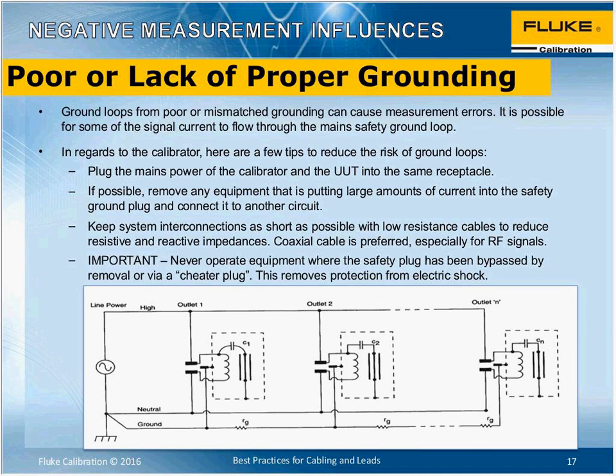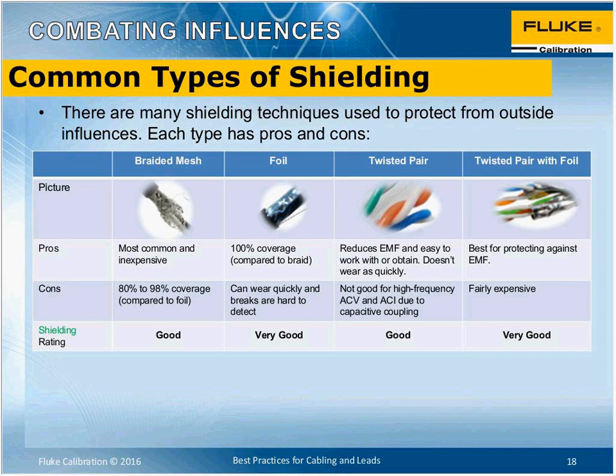But there's often a temptation to break a ground loop by disconnecting the ground earth cable, the safety earth, and that's never a good idea, because while it might break the ground loop, it does put you at risk of electric shock. So breaking or cutting the wires or using those cheater plugs is not a good idea. There are much better ways to avoid ground loops by doing some of the things we've just talked about, rather than putting you and your staff at risk of electric shock.